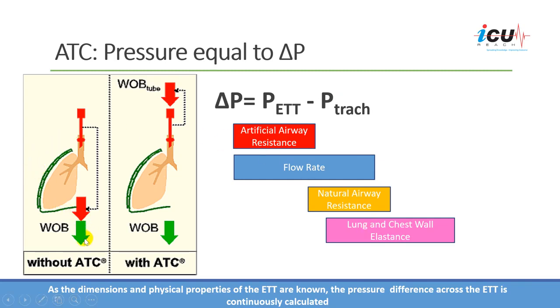Without ATC, the patient has to do the work to overcome the artificial airway resistance. With ATC, we transfer that work to the ventilator — the machine provides the pressure needed to overcome the artificial airway resistance.